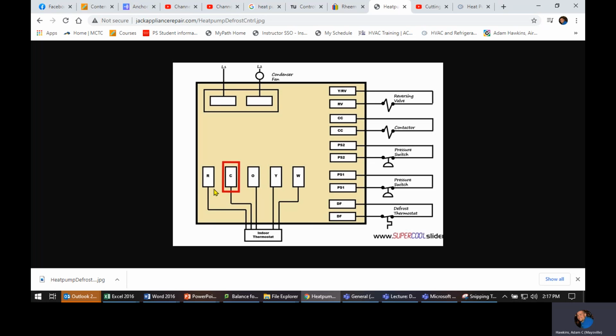So you've got red coming from a stat. Actually, your red is going from the air handler, not from the stat. So the air handler is your hub. The air handler is where your power is coming from. So your red and your common are feeding back to your transformer. Your red is feeding your thermostat, and then your thermostat is telling everything on its end what to do. So if it's saying we're calling for heat, we're calling for cooling, whatever, then it's sending that 24 volts from red to all those places.